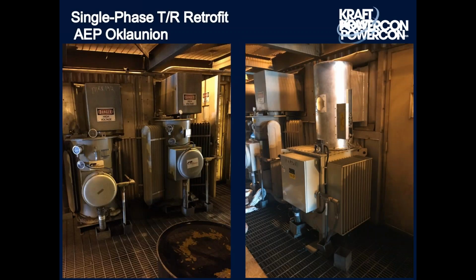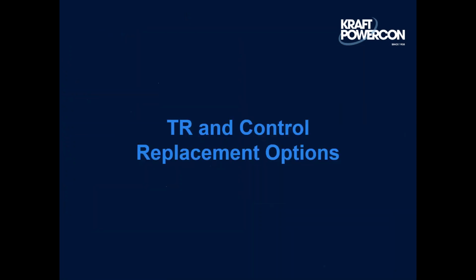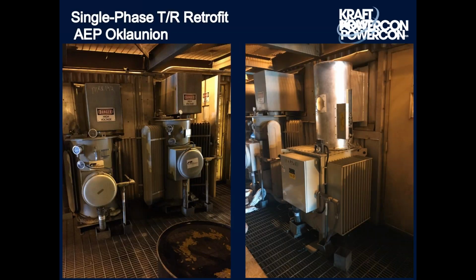Next slide. So these were some of our direct replacement retrofits. I noticed our logo's messed up there, but that's okay, sorry about that. This was a GE-designed TR set - they've operated very well, and I think this precipitator is 40 years old or greater. The difficulty with the GEs is that this is a Lodge-Cottrell precipitator, as you can see where they have the penthouse next to it, with the bus duct connecting through the side wall. There is no replacement.